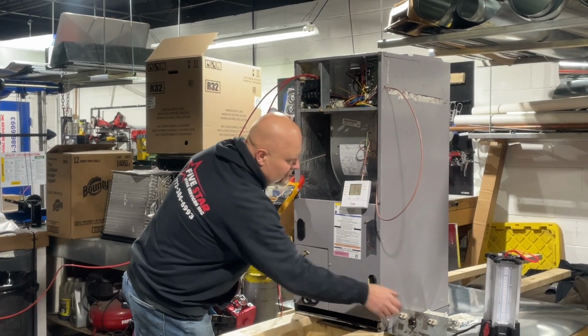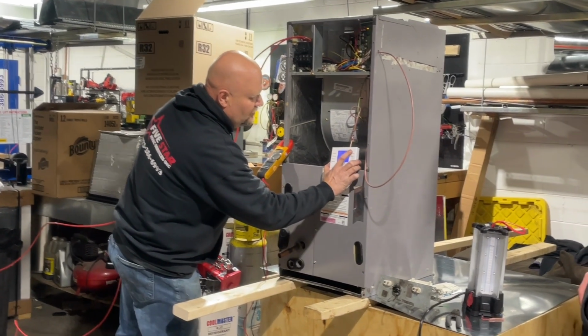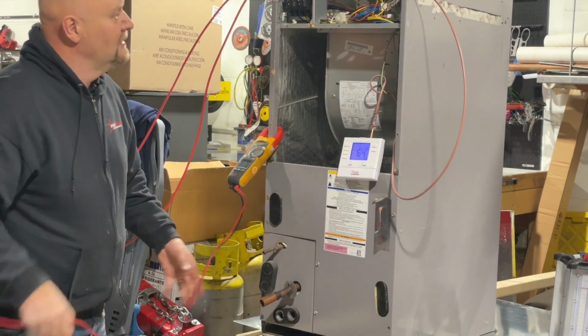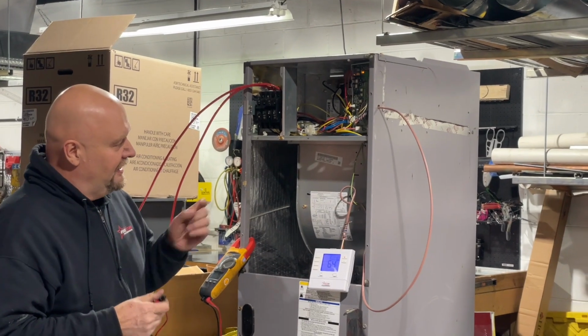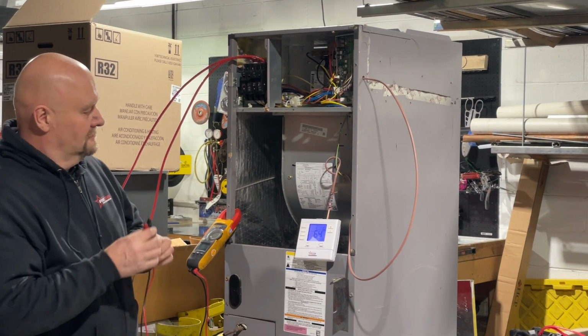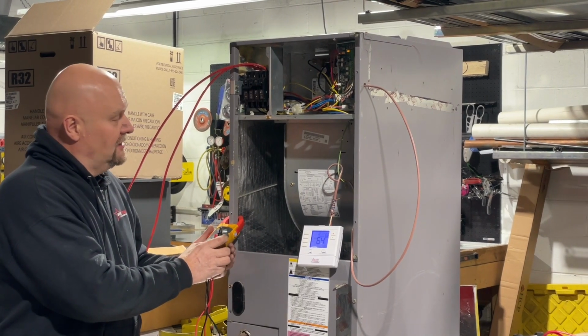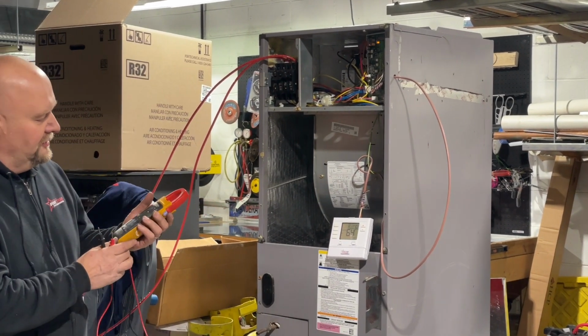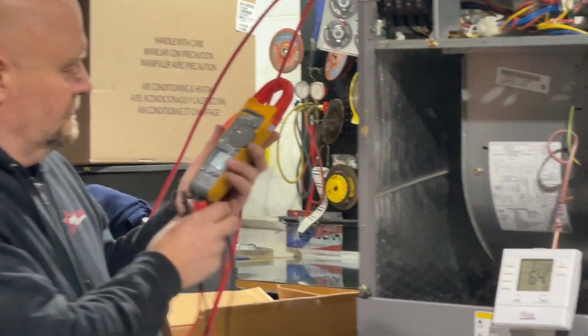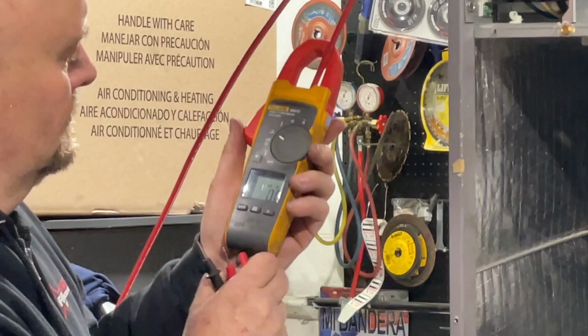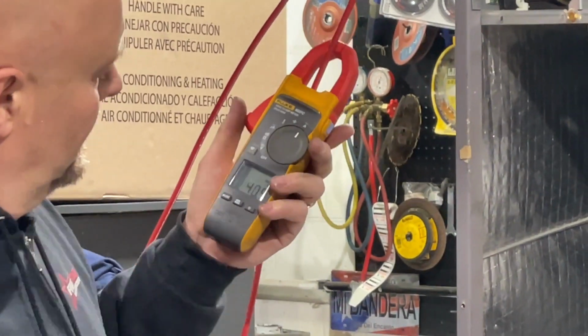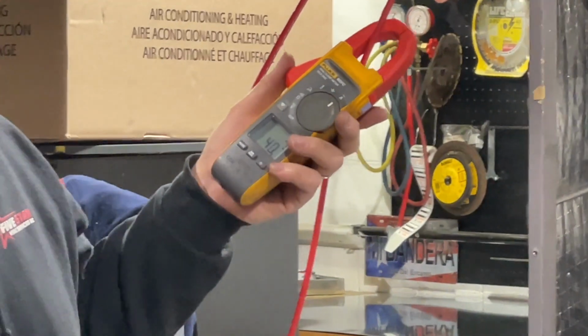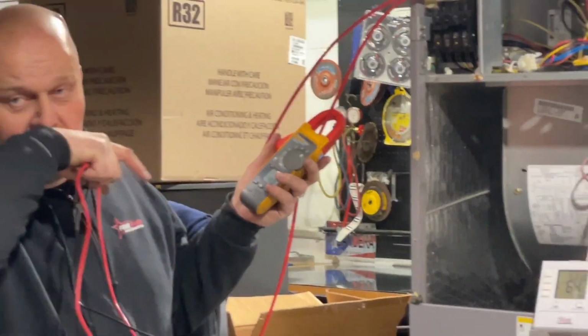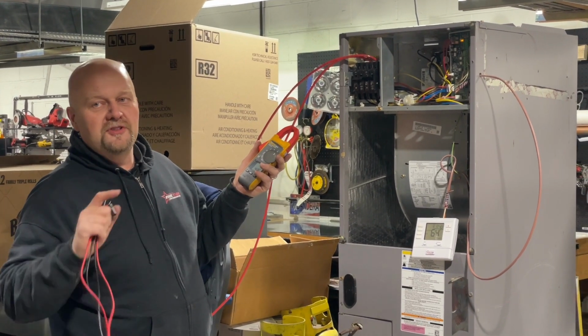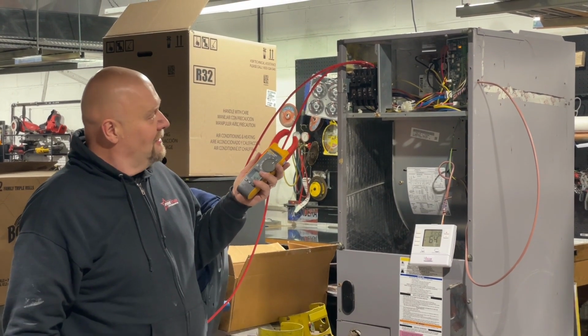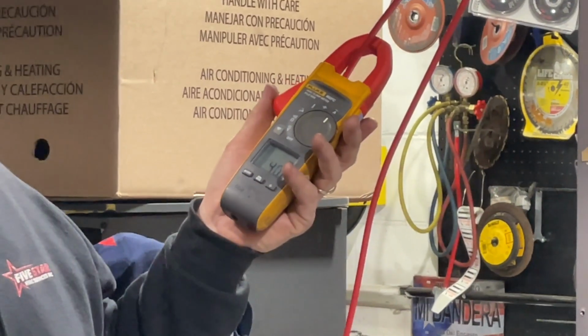So I'm gonna turn the heat on. It's too warm in this place. So now let's see if when the heat comes on, this should instantly fire up our fan. See? The fan's gonna come on. And now I'm gonna switch my meter from voltage to amperage. So right now I'm reading 40 amps, right? You're gonna notice, and I know you're gonna ask me this, it's not 40 times 2. You're gonna read the amperage of the entire circuit, because this is one big circuit. So now as I switch to this side, you're gonna see 40.3 amps, the same thing, okay?